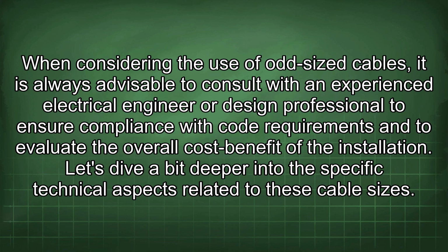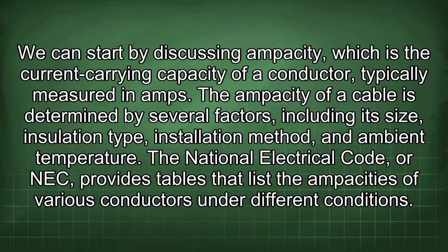Let's dive a bit deeper into the specific technical aspects related to these cable sizes. We can start by discussing ampacity, which is the current carrying capacity of a conductor, typically measured in amps. The ampacity of a cable is determined by several factors, including its size, insulation type, installation method, and ambient temperature. The National Electrical Code, or NEC, provides tables that list the ampacities of various conductors under different conditions.